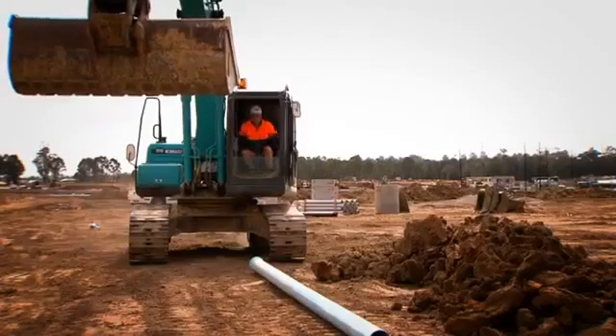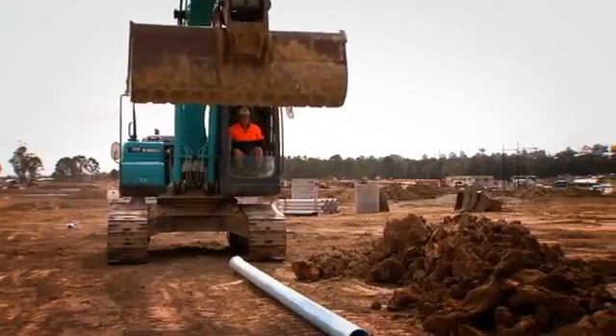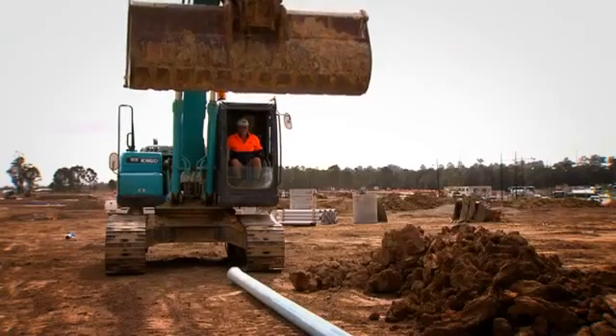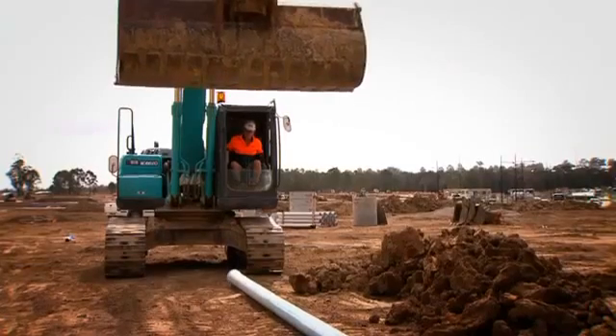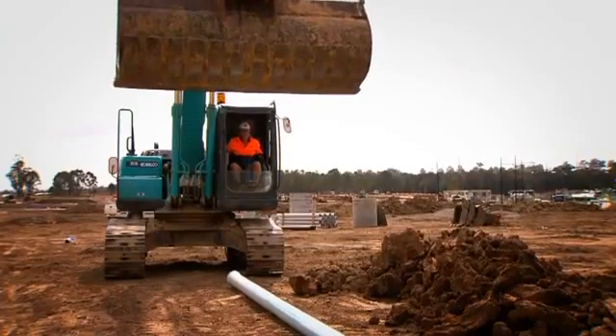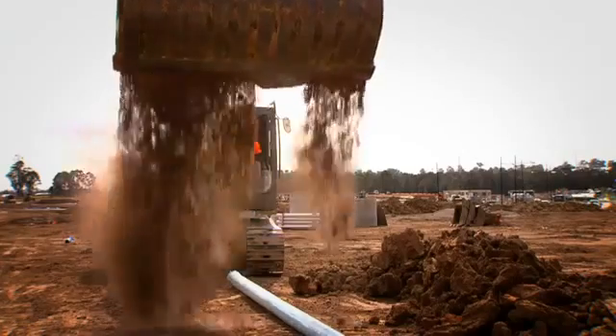The abuse did not end there, however. Everyone was keen to subject the pipe to extreme field installation conditions. An excavator was used to lift a rock weighing approximately a quarter of a tonne to a height of two and a half metres above a length of 150mm PVCO pipe. The rock was then allowed to freefall directly onto the PVCO pipe.